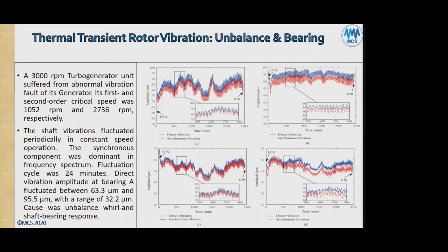So they considered that it was a thermal whirl, or a mechanical whirl caused by unbalance, but it introduced thermal effect at the bearings. And they considered the shaft would get hotter at certain parts of the shaft and inside those bearings. I don't really have a good idea and good drawings of the whole machine and the bearing for me to judge that part of what they considered the cause.